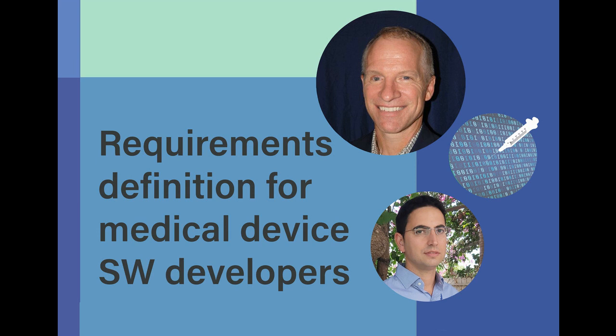And within design validation, you will see this topic, risk management, come up. So that's where everything we do associated with safety risk management comes about, because of that design validation requirement in the regulations. But what you begin to understand about risk management is it's not something that's done late in the process, and only done really as part of design validation. It's really done throughout the process.